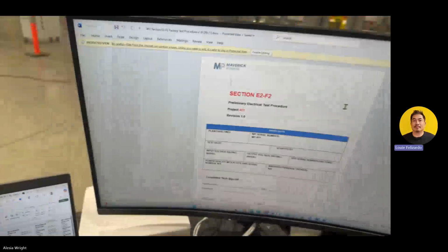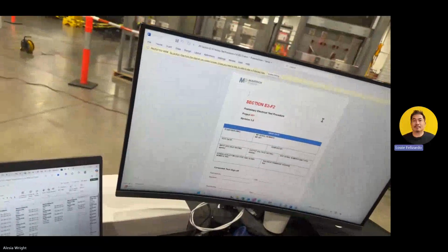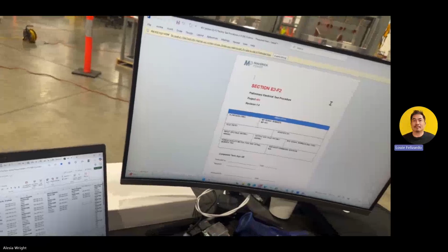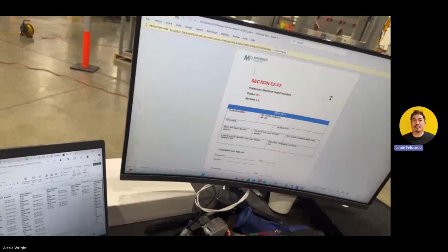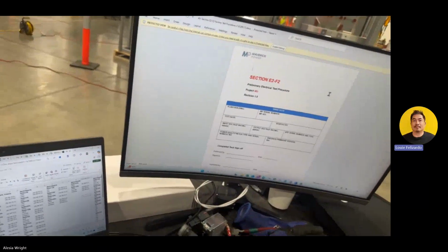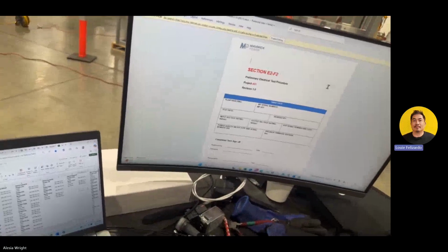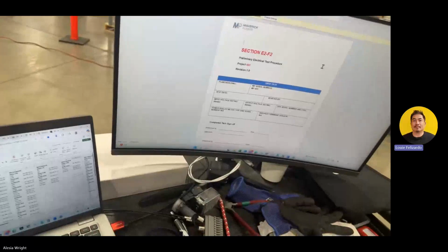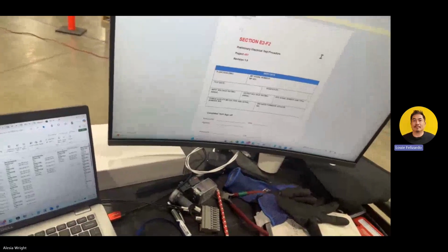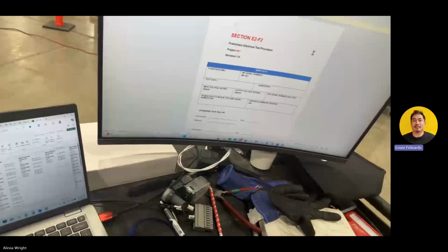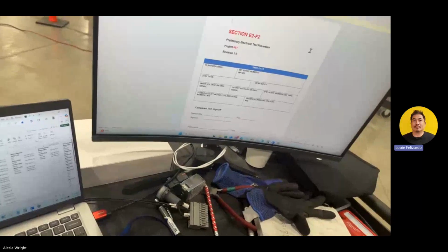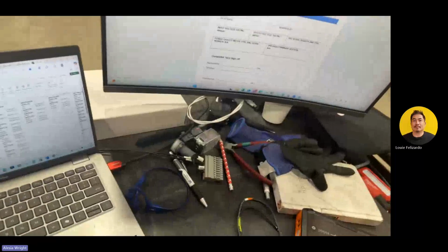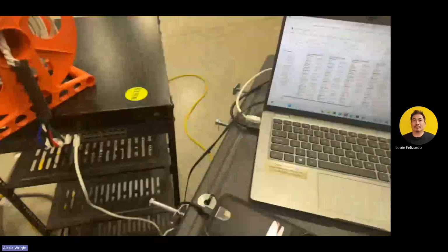Okay. So one last question for your infrastructure, meaning your networking. For this one unit, this one PDU that we're doing validation on, are you guys doing the same thing? You connect to the Turck, the HMI, and the breaker. They all connect through RS-485, I think, to a switch that's connected to your laptop. Exactly. Okay, so I'm gonna turn around. I'm gonna show you how it's connected.